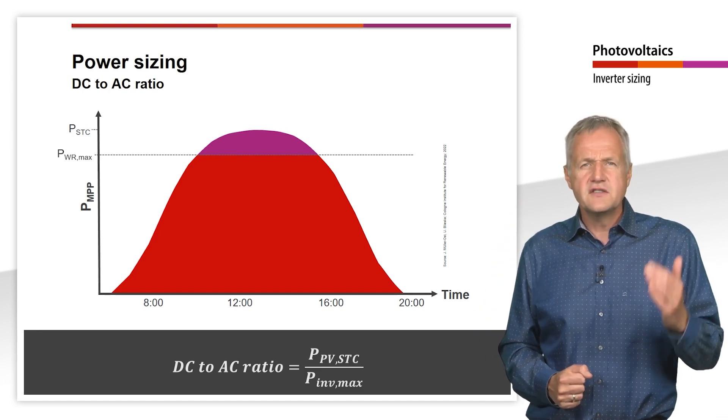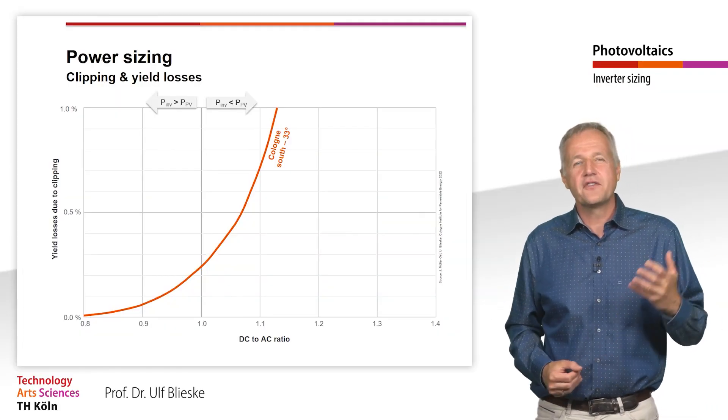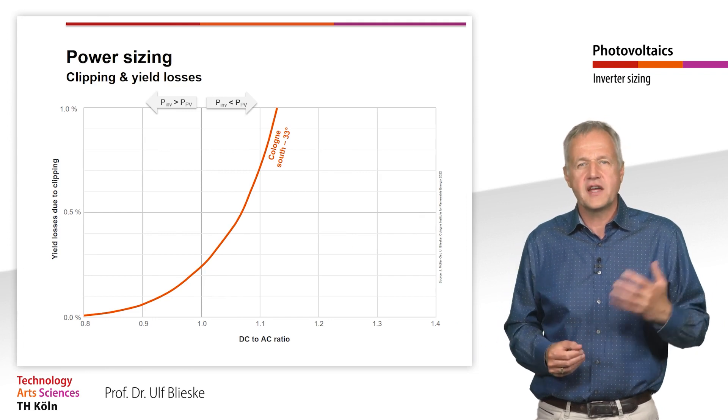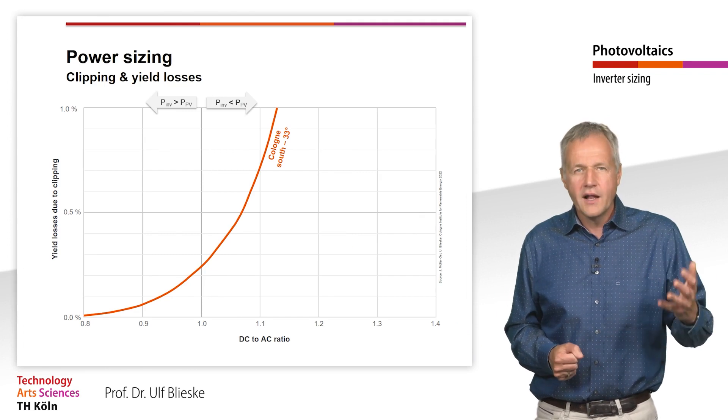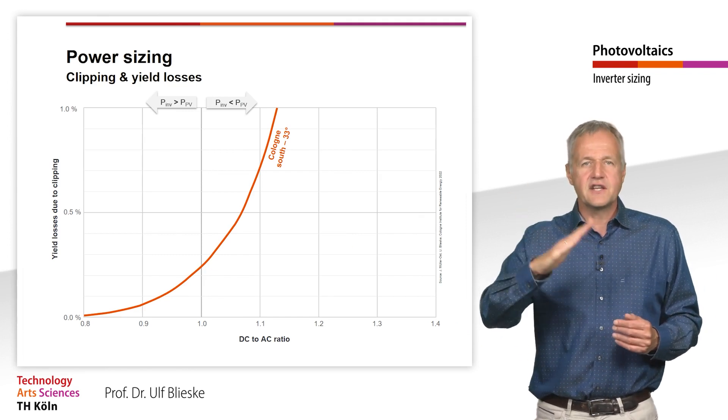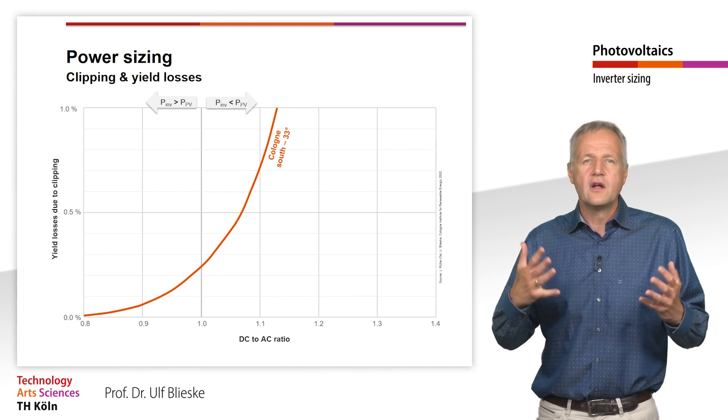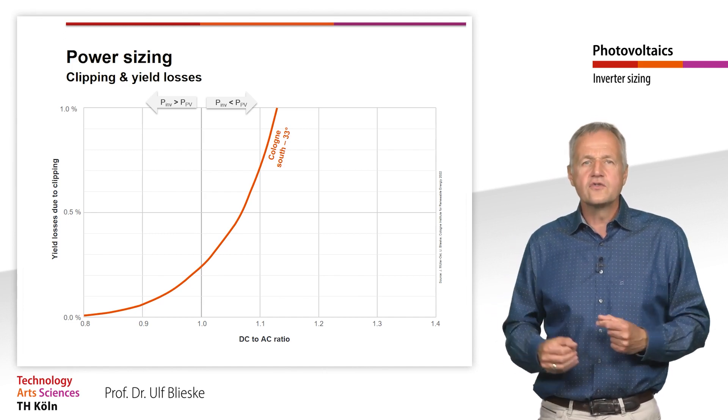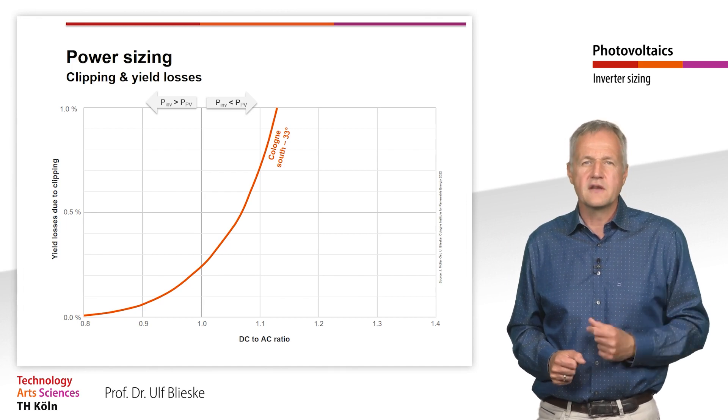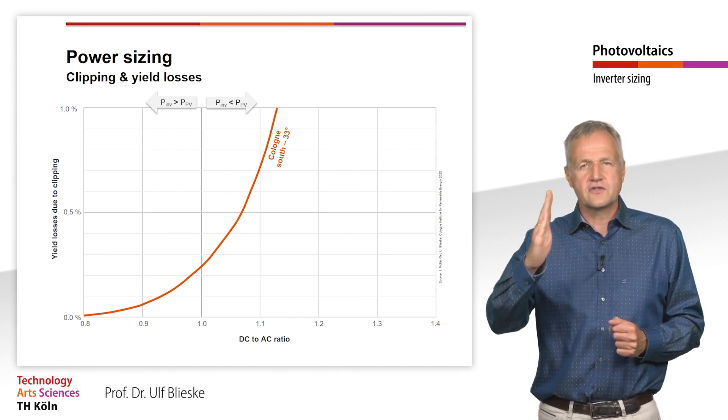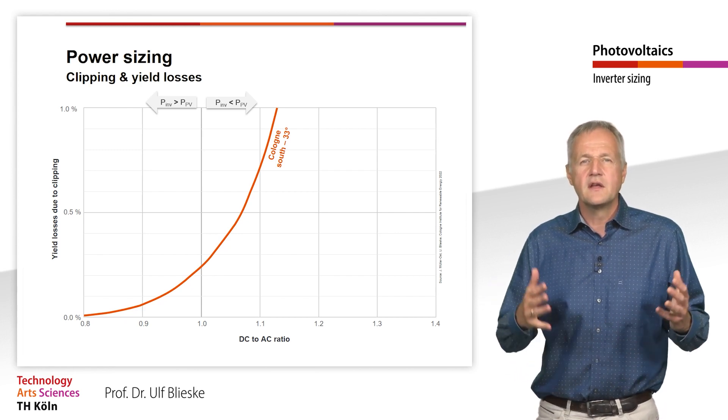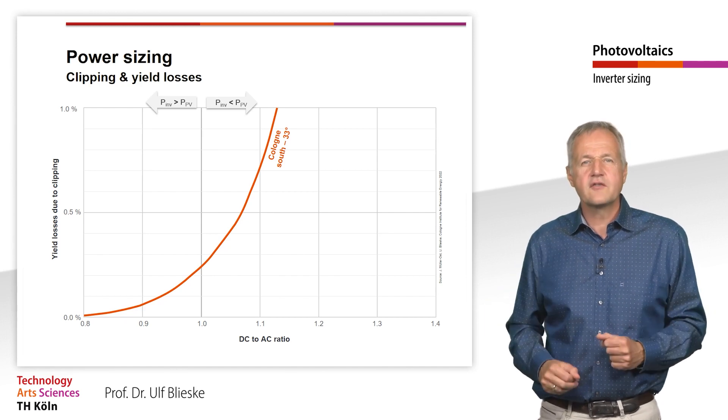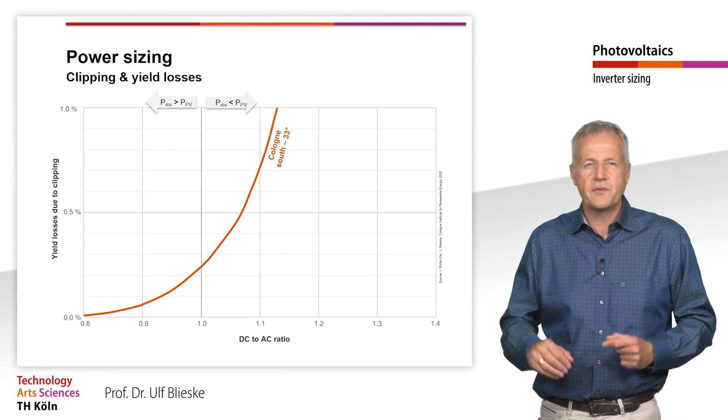But which DC to AC ratio is optimal? This question cannot be answered in general because the answer depends on the temperature and the irradiation conditions at the location as well as on the orientation and the inclination of the modules. Let's take a look at this using the example of a plant in Cologne, Germany, which is oriented to the south and has an optimal tilt angle of 33 degrees.